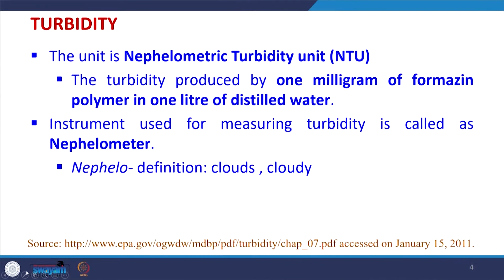For any turbidity nephelometer, we make a calibration graph by dissolving different amounts of formazin in distilled water, and then we measure the light that has been scattered. Through that light we draw the calibration graph, and later on for unknown samples we determine the turbidity using this nephelometer. Just for the definition's sake, nephelo means clouds or cloudy. Clean water has turbidity of less than 1 NTU. NTU means nephelometric turbidity unit.